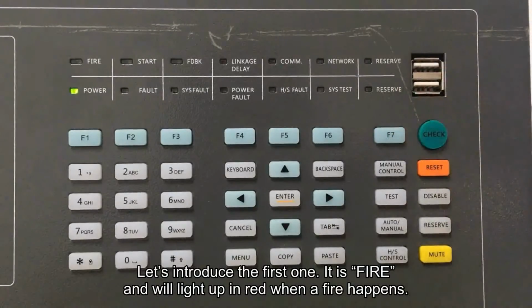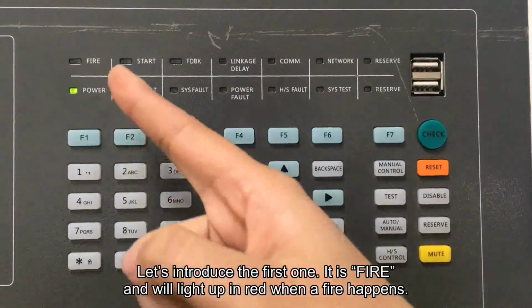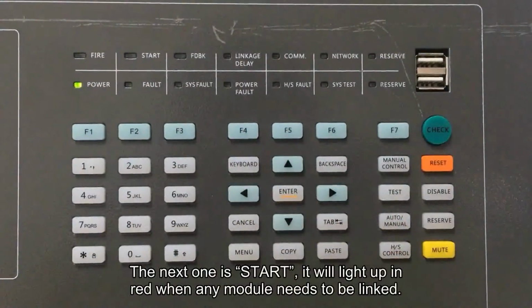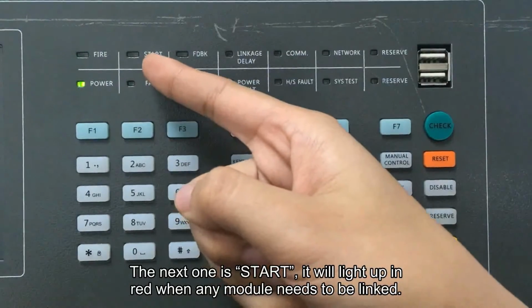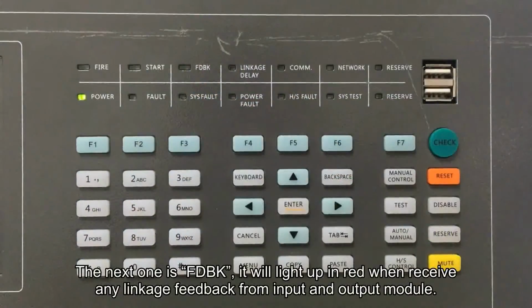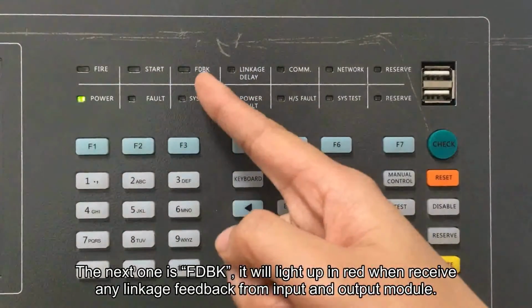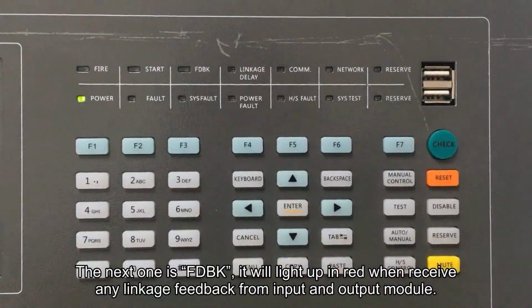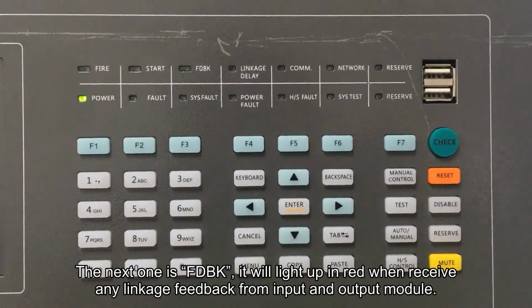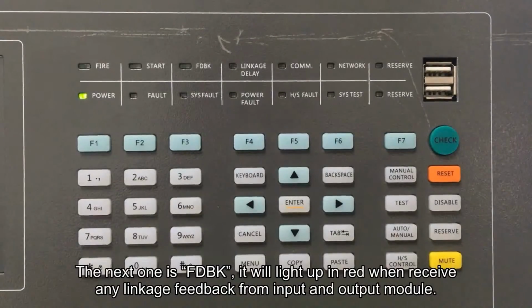Let's introduce the first one. It is fire, and will light up in red when a fire happens. The next one is start. It will light up in red when any module needs to be linked. The next one is FDBK. It will light up in red when receive any linkage feedback from input and output module.